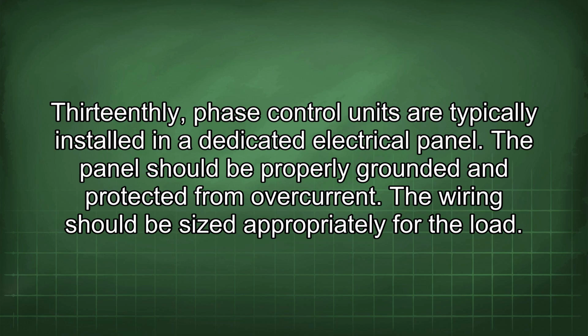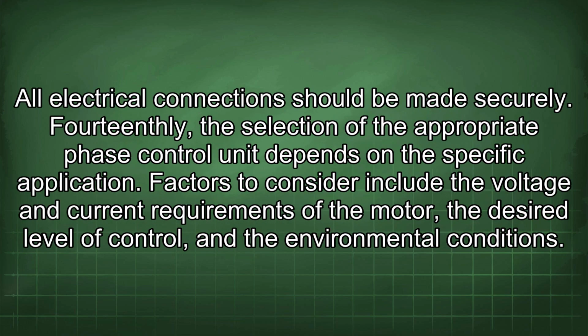13thly, phase control units are typically installed in a dedicated electrical panel. The panel should be properly grounded and protected from overcurrent. The wiring should be sized appropriately for the load. All electrical connections should be made securely.